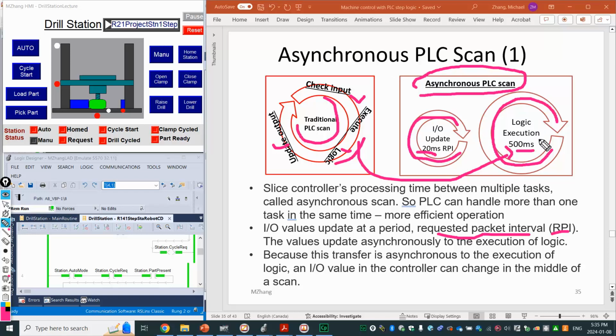Some part of your logic at the beginning may check the I/O sensor and find it off, but right in the middle, because the I/O scan runs more frequently, your input may change state even in the middle of logic execution. That's a big problem - if the I/O changes status mid-execution, it becomes inconsistent for your logic.